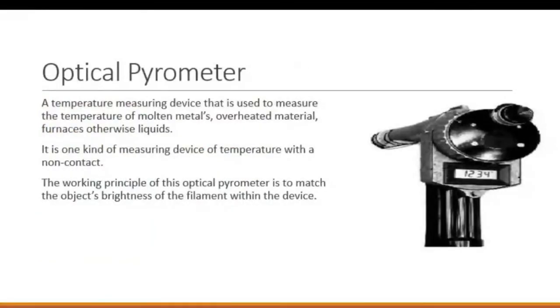Optical pyrometer. Optical pyrometer is used to measure temperature. It is a non-contact type pyrometer. In certain situations, like measuring the temperature of molten lava, it is not possible to measure by making physical contact with a thermocouple. The thermocouple will fail to do the operation. In such a case, an optical pyrometer is used.